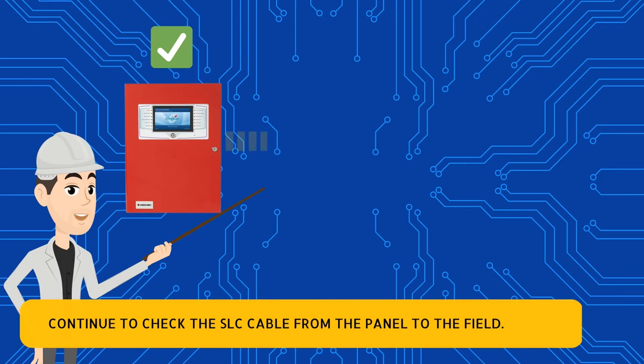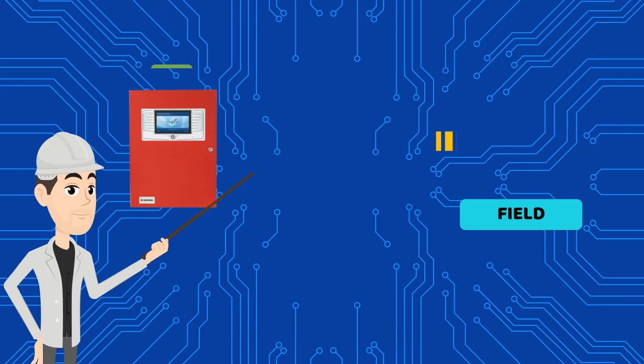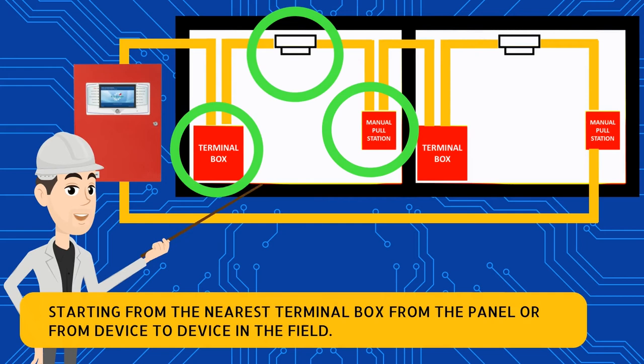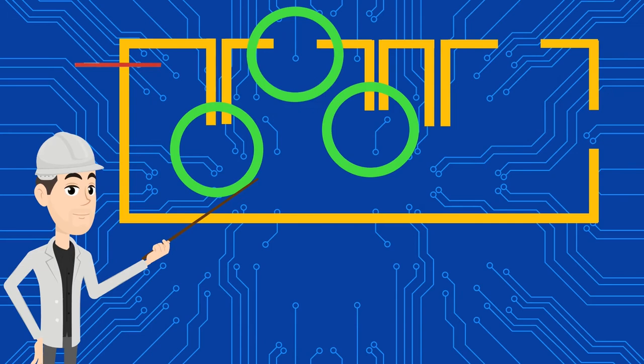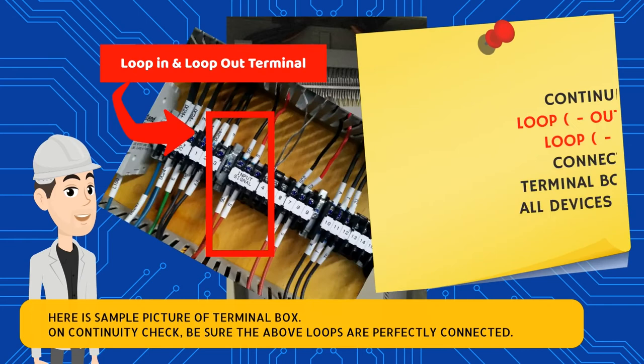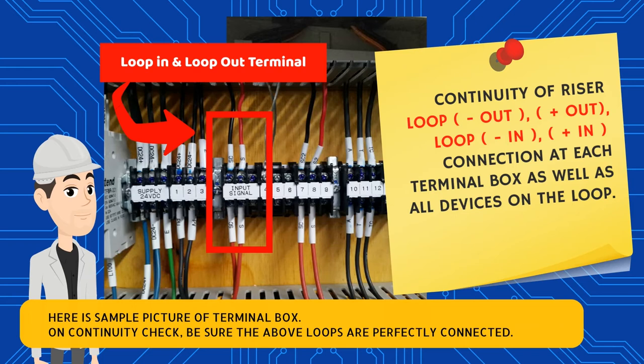If the SLC cable in the panel area has been confirmed to be connected correctly, continue to check the SLC cable from the panel to the field. Perform a continuity check on the SLC line in the field, starting from the nearest terminal box from the panel or from device to device in the field. Here is a sample picture of a terminal box. Once on the continuity check, be sure the loops are perfectly connected.